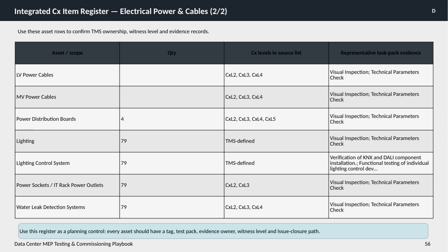Looking at the table, you can see various assets listed, such as LV and MV power cables, power distribution boards, lighting control systems, power sockets, and water leak detection systems. Each asset is assigned specific commissioning levels, ranging from CxL2 up to CxL5, depending on complexity and criticality of the component. For example, power distribution boards require the highest level of commissioning, including level 5, while power sockets primarily require levels 2 and 3. The representative tasks for each asset involve visual inspection and technical parameter checks to ensure everything is installed and functioning correctly.